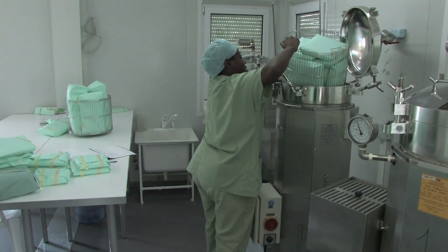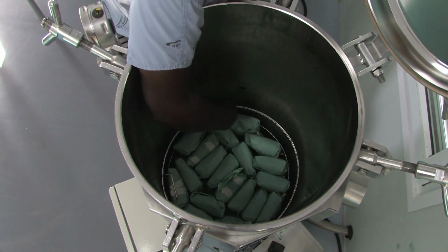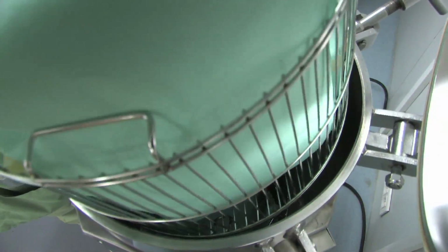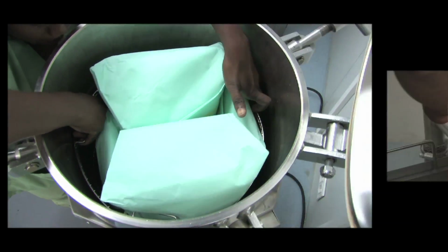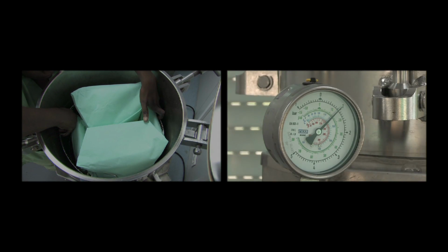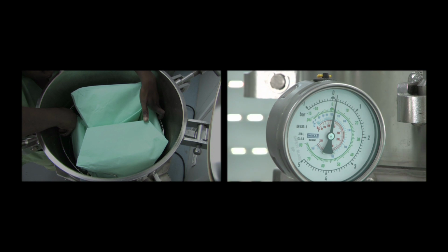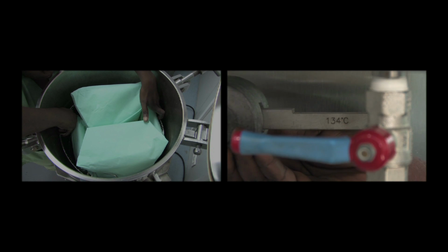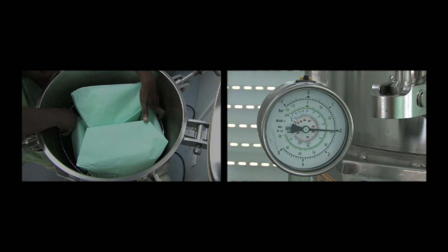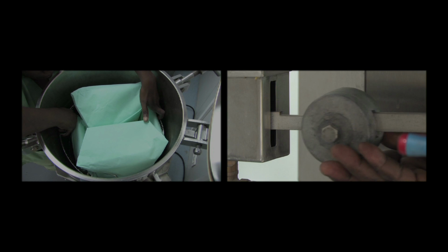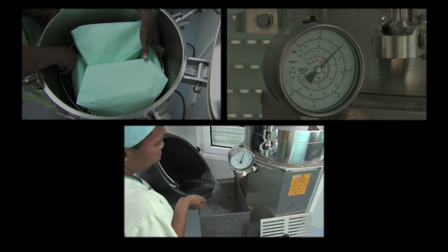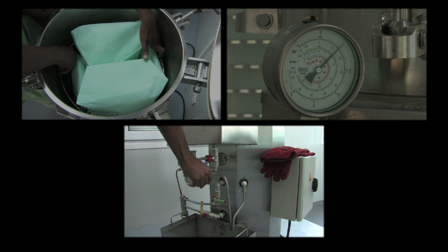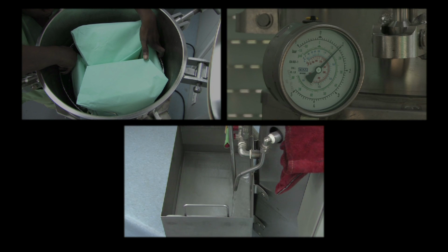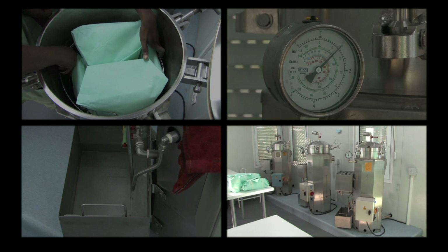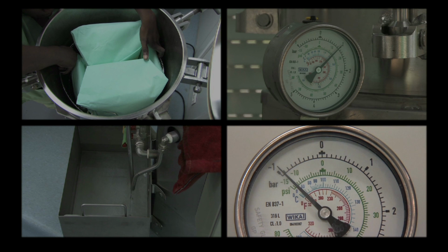Use the baskets to prevent the packs from touching the walls. Do not overload the autoclave. Always do 3 purges. Respect the sterilization plateau duration, that is 10 minutes at 134 degrees Celsius and 2 bars, or 30 minutes at 121 degrees Celsius and 1 bar. Add 2 rounds of cold water to cool the steam. During the drying phase, leave the autoclave closed and at negative pressure.